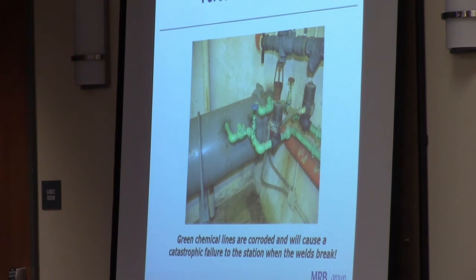Well, and then to your point, Paul, we're estimating the thickness of those pipes has rotted close to 40 to 50%. 2 years ago, I had the guys go out and clean them and start spraying them every month with galvanized spray to try to slow it down. And we did that for 4 to 5 months to try to maintain it, as Paul said. When they fail, there's no stopping.